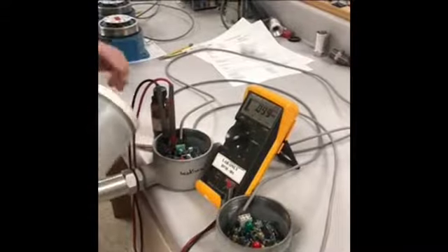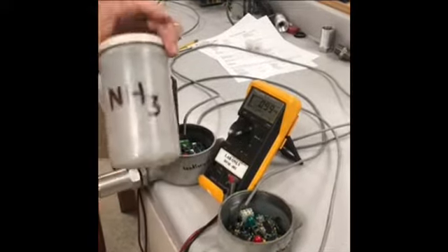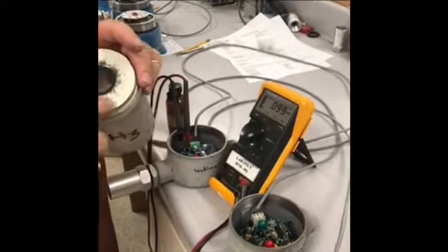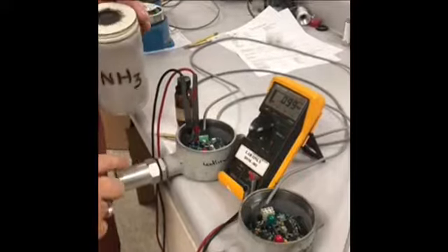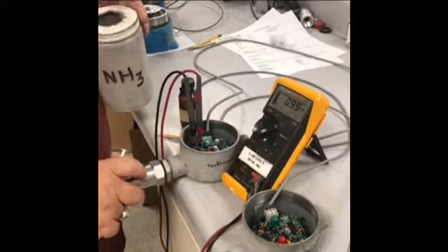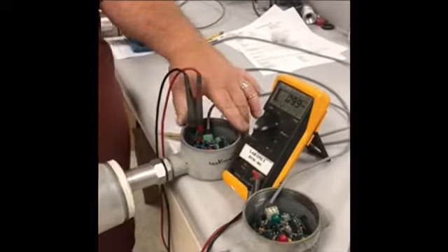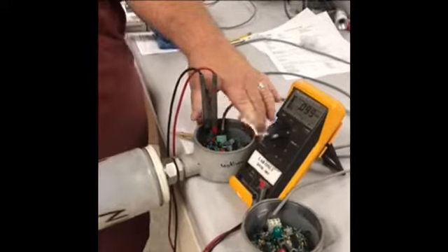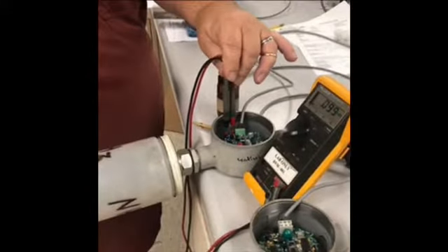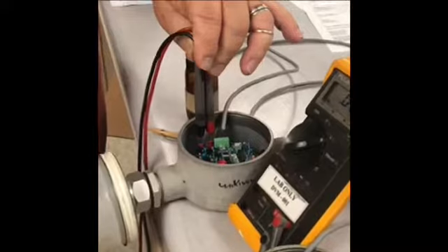Okay, at this time I'm going to show you how to calibrate the sensor using the calibration canister. It has the top on it with a rubber septum that fits over the rain shield of the SM95. You want to go ahead and put the canister over the rain shield. We've got our voltmeter probes measuring the output of the transmitter.